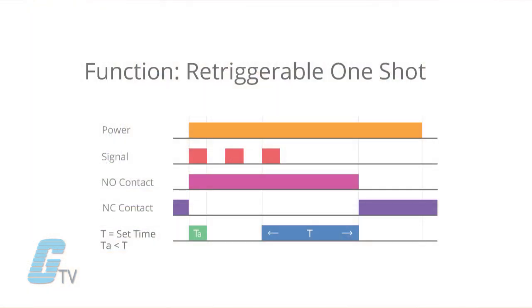The one shot timer can also be available as a retriggerable one shot where the timing begins every time the signal is introduced. When the contacts are in the on state, application of another signal input will reset the timer and timing will begin again.